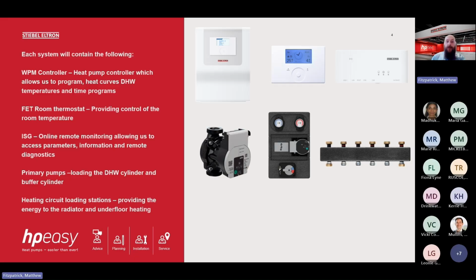Next up, we will have a room thermostat. So we have our FET room thermostat. Now, most heat pump systems are normally operating on a weather compensated curve. The colder it gets outside, the more energy the heat pump puts into the property and into the system. But we all like different temperatures. You speak to different people and people are happy at 18 degrees, 20, 21, 24. So we need to ensure there is a balance in the property. Now, having the room thermostat allows us to not only override the weather compensated curve with a marginal factor, but also provide the higher comfort levels that we're used to with fossil fuel heating systems.